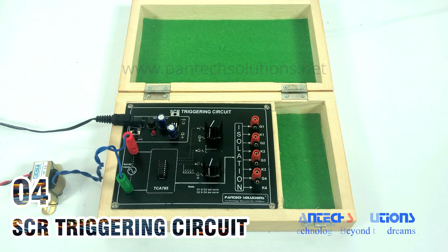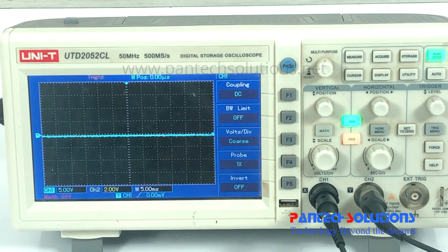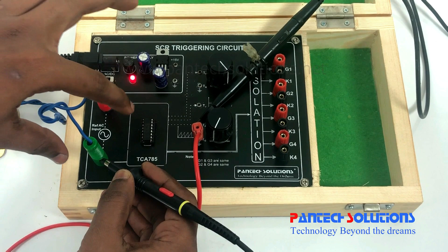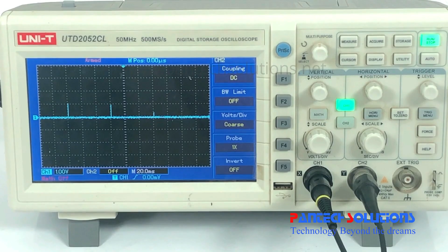This ramp signal output and DC signal output are both compared and will generate the triggering pulse, the gate pulse of the SCR triggering output. One probe is input AC and another is the ramp signal. The ramp signal is generated with reference to the input AC supply. This is the triggering output of each SCR.